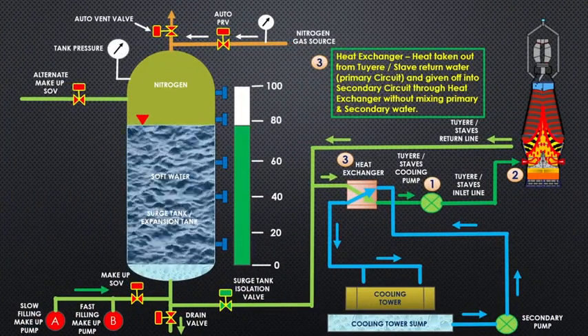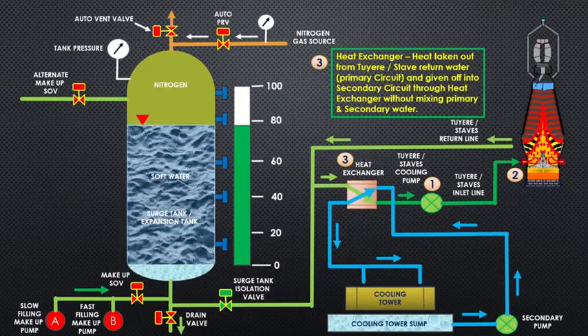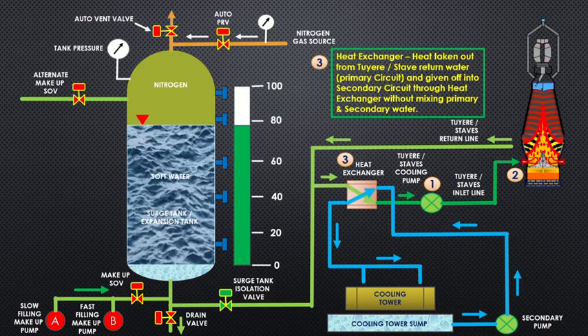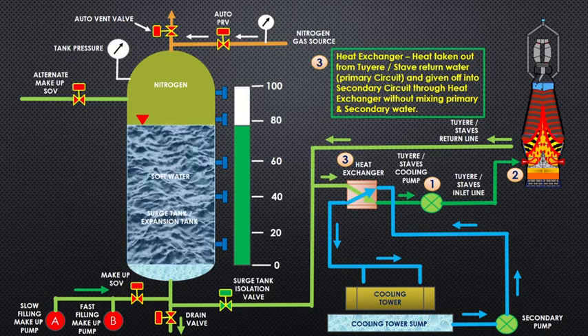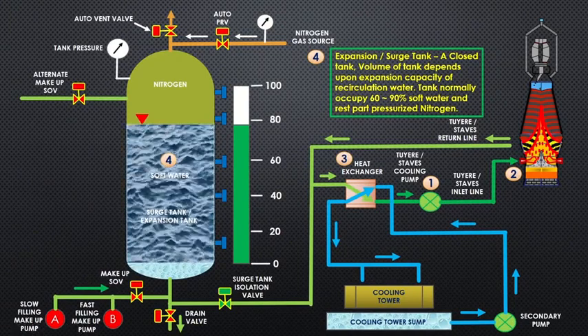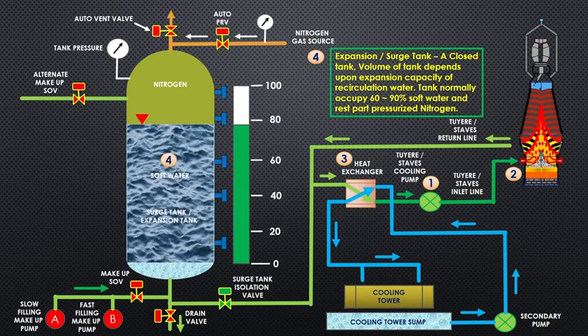Heat exchanger: heat taken out from tuyere or stave return water or primary circuit and given off into secondary circuit through heat exchanger without mixing primary and secondary water. Expansion or surge tank: a closed tank, volume of tank depends upon expansion capacity of recirculation water.